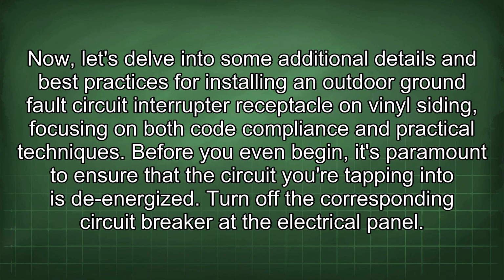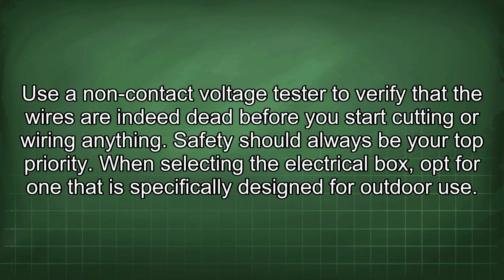Now, let's delve into some additional details and best practices for installing an outdoor ground fault circuit interrupter receptacle on vinyl siding, focusing on both code compliance and practical techniques. Before you even begin, it's paramount to ensure that the circuit you're tapping into is de-energized. Turn off the corresponding circuit breaker at the electrical panel. Use a non-contact voltage tester to verify that the wires are indeed dead before you start cutting or wiring anything.